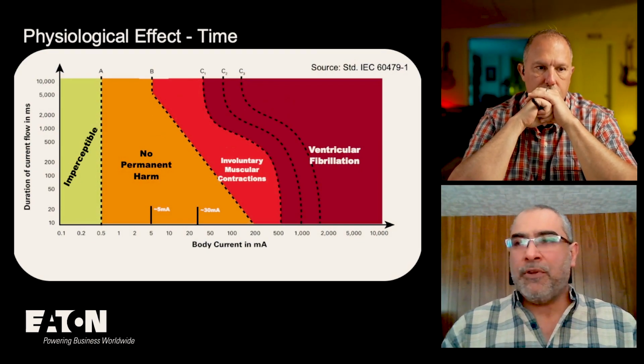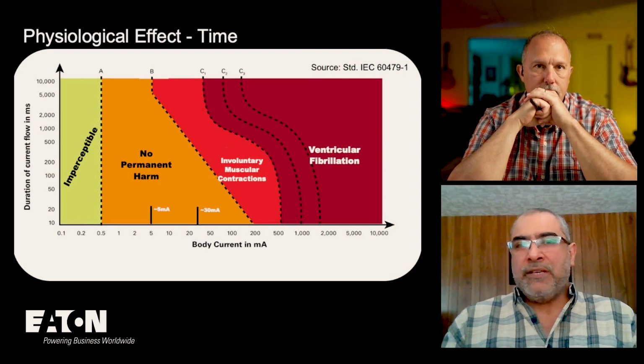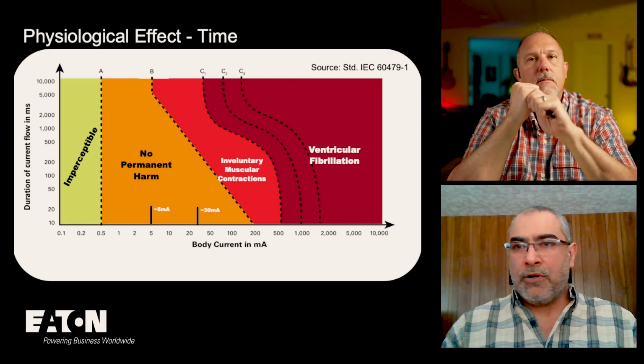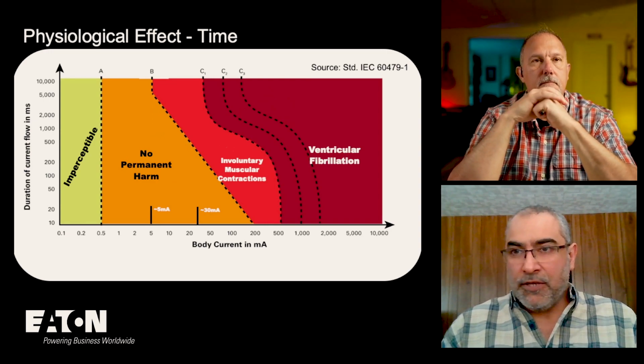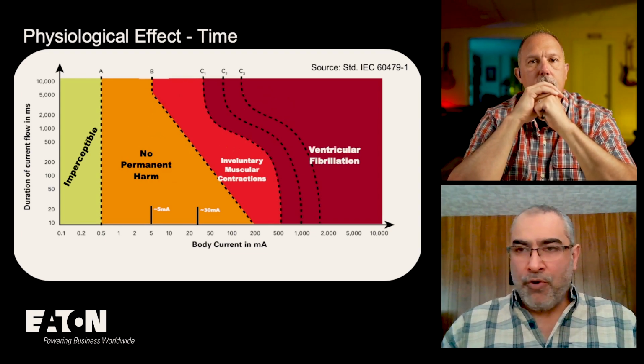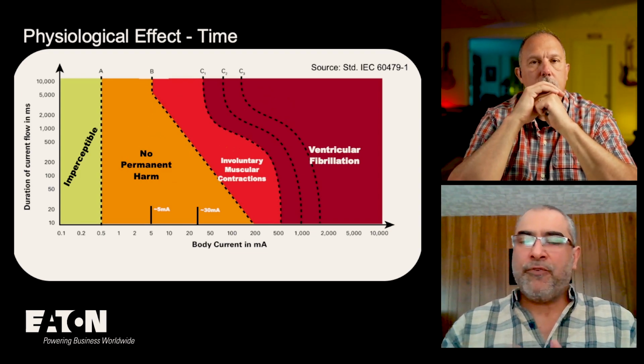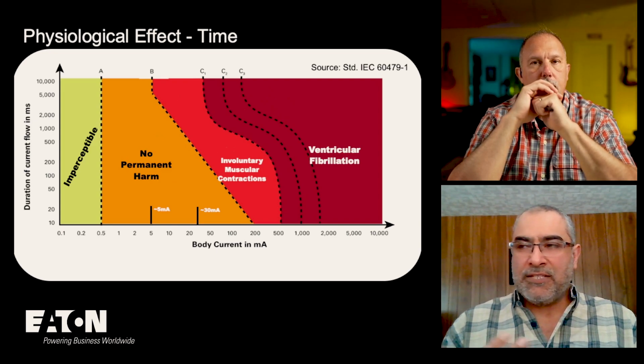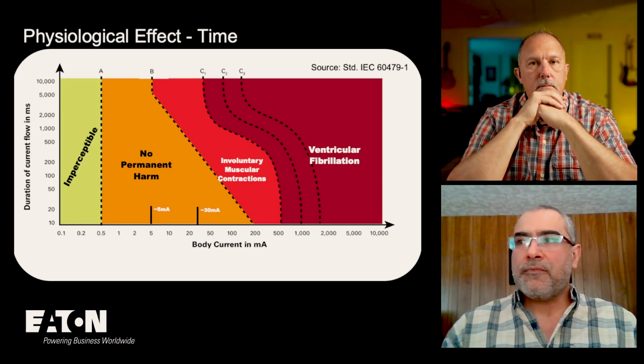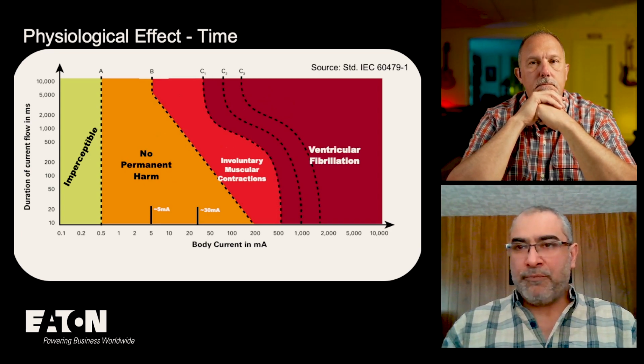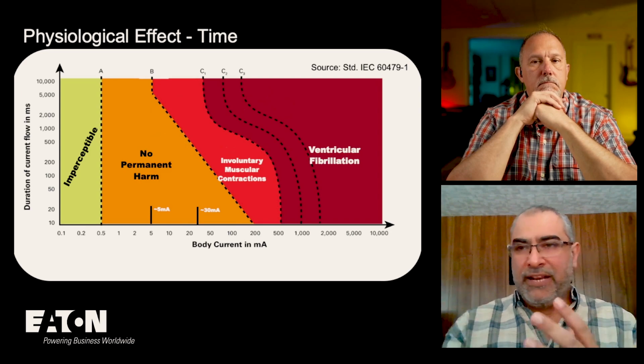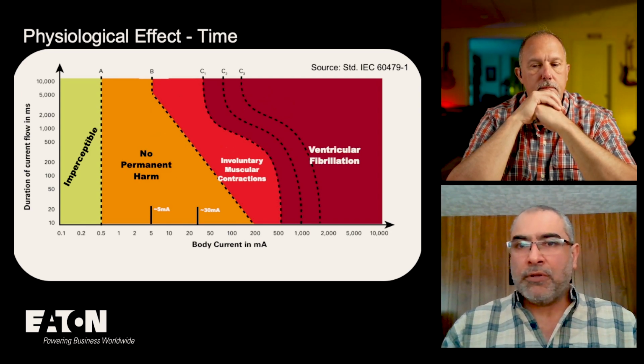This is why GFCIs are required to respond really fast. At the end of the day, a GFCI is just a ground fault detection method, very similar to a ground fault relay. The problem is we cannot tolerate the same current that a motor or pump can tolerate. So if you're protecting a motor or equipment from a ground fault, it's the same theory of operation and detection method that a GFCI and a ground fault relay use to detect a ground fault current.